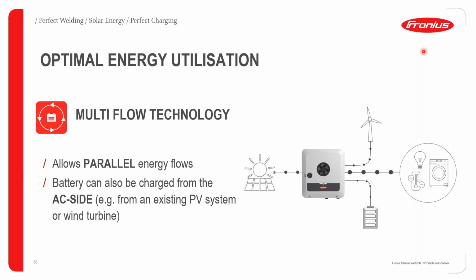Having said all that, the Gen 24 also offers a very unique possibility for something that we call multi-flow energy utilization. This multi-flow technology is integrated as a standard in the Gen 24 inverters, whether single phase or three phase. It basically means that we can have power flowing in multiple directions, as we can see in this graphic here. We have a possibility to generate PV power, and at the same time, we are drawing from the battery system if what is coming from the PV power is not sufficient. We could also have an independent source of AC power, maybe a wind generator or a third-party inverter, which is also feeding into the Gen 24 inverter in an AC coupled configuration. And this is consequently supplying the required or connected load at that particular point.